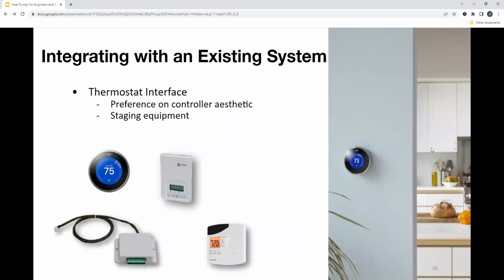So integrating with the existing system, I know I had a slide on this back, but this is kind of related to two things, right? First thing would be if I'm using a heat pump system and I do not like any of the local controls that any of the manufacturers have, I do like this Nest or a different type, I would select a thermostat interface. What I'm able to do is connect the heat pump to this Nest, and the Nest can control the heat pump accordingly, right? So that would be one option. Aesthetic is big to some people.